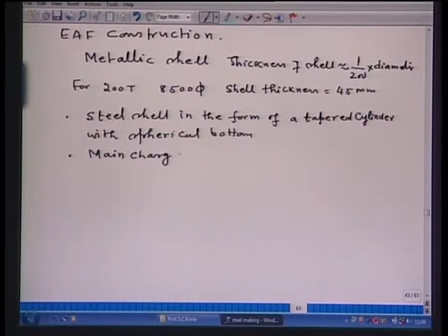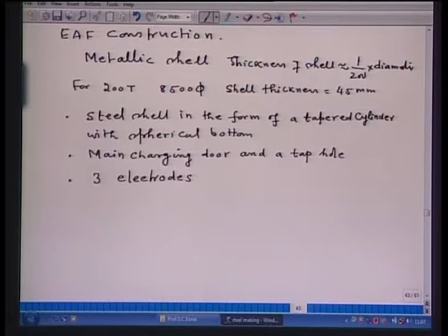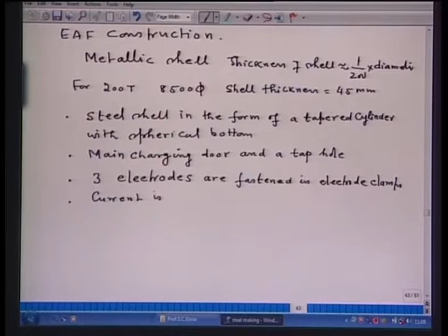Then AC EAF works with 3 electrodes, whereas DC EAF works with 1 electrode, or rather 1 graphite electrode and 1 separate anode, which is built at the bottom of the electric arc furnace. AC EAF works with 3 graphite electrodes and they are fastened in electrode clamps. The diameter of the graphite electrode is of the order of 400 to 700 millimeter. It's a quite heavy electrode. Fourth, current is supplied by water cooled cable.